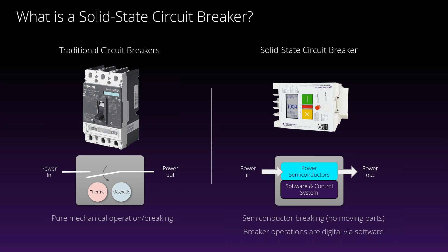And so where does this compare to traditional mechanical breakers? And some of these metrics here, like endurance, since you're not actually mechanically opening and closing anything, a solid state circuit breaker can have millions or tens of millions of operations under full load and not see any degradation to the equipment. Every breaker that we have UL listed is rated for 200,000 amps of fault current. It's kind of unheard of in a circuit breaker. Normally you would need a fuse to get that kind of rating. And at the same time, the let through current at 200,000 amps is less than 1,500 amps of peak let through current, which is, if you're familiar with this, incredible. It's lower than any current limiting fuse on the market today.